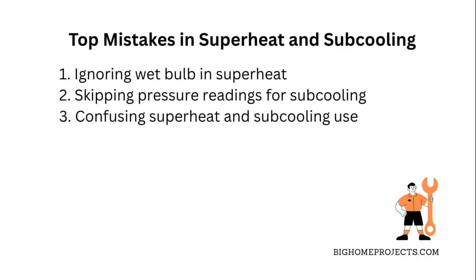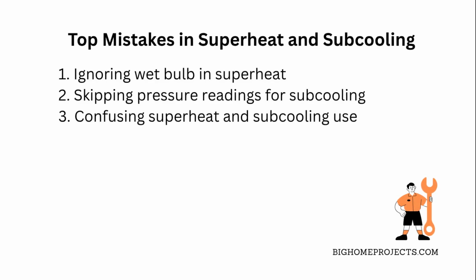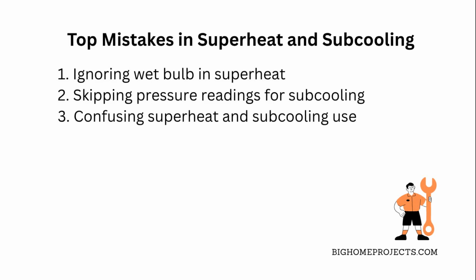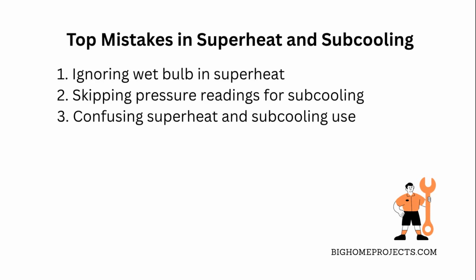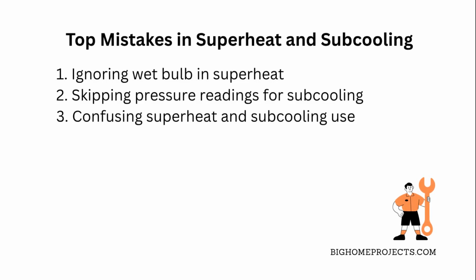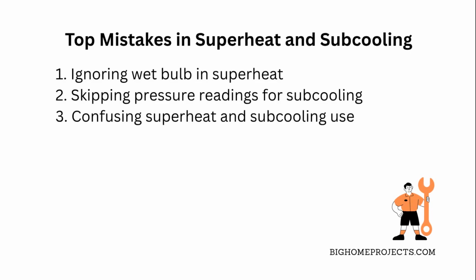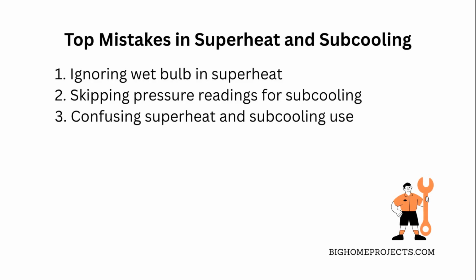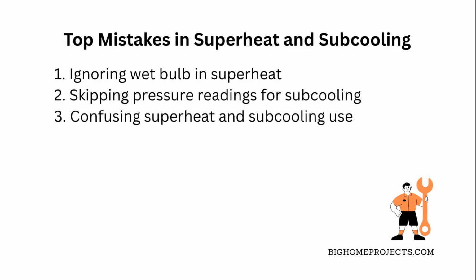One of the biggest mistakes people make with superheat and subcooling is ignoring the wet bulb temperature during superheat checks. This leads to wrong heat load assessments and can cause compressor damage. Fix it by always measuring indoor wet bulb temps accurately. Another common issue is relying solely on temperature without pressure readings for subcooling, which can mask refrigerant charge problems. To fix this, use a good gauge set to get both pressure and temperature data.